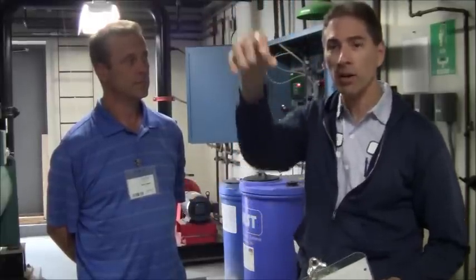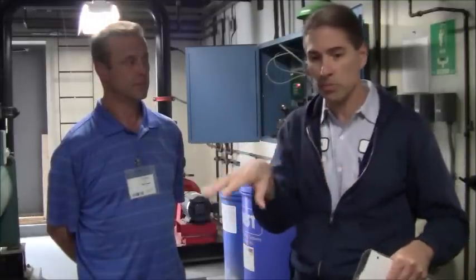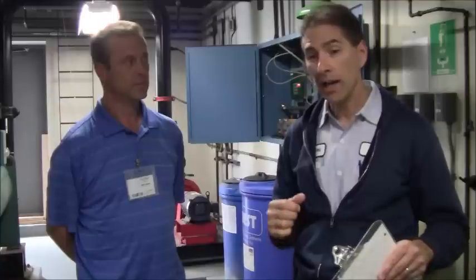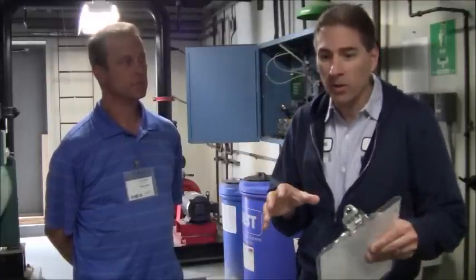So at the top of the cooling tower, the water comes down, it goes through some type of spray distribution nozzle system in which it can go over the fill and disperse over a large surface area to release the heat. And because of that, you have air coming across it, air from the outside. That water, the open loop water, is now exposed to the outside elements, and in that environment, it has the ability to catch much more debris than the closed environment, almost like a clean room environment, which you can really control things with. But with the open loop, that's why much more care is needed in an open loop compared to a closed loop. So that's just an FYI on how you tell the differences and why the open loop requires much more TLC than a closed loop.